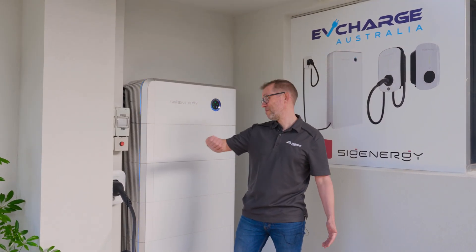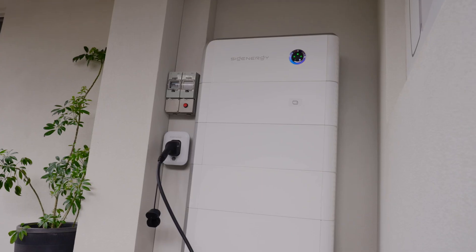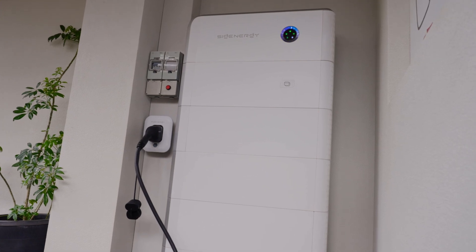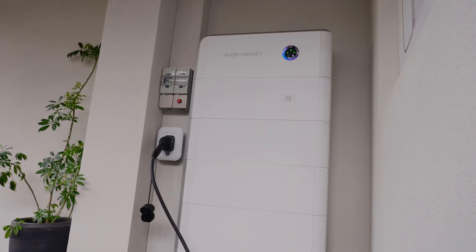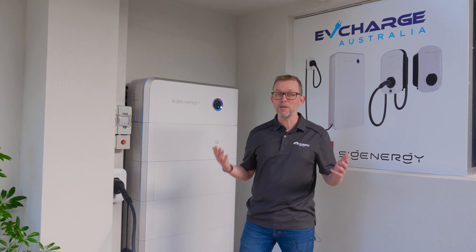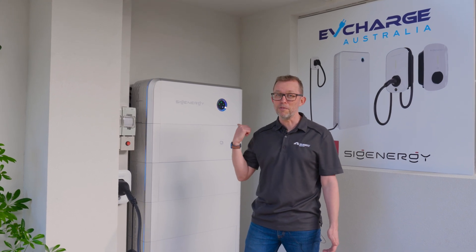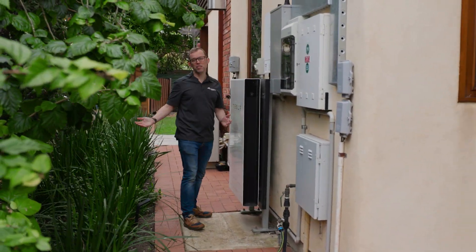It's fully installed — it took four and a half hours. Can we just take a moment to appreciate how neat that install is? Compare that to installs where you've got all separate boxes all over the place. That's all thanks to the boys at EV Charge Australia and this beautiful custom ducting. One limitation of the Sigenergy DC EV charger is it's attached to the battery stack, so if your battery is a long way away from your car, it's just not going to work for you.